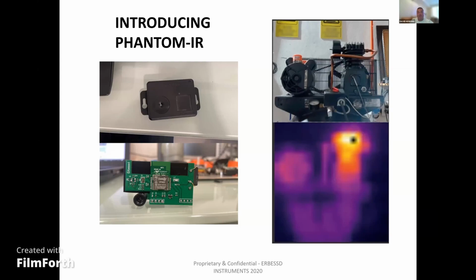The alternative to wearing the arc flash protection is infrared windows. Well, infrared windows are great, but they're also expensive and they require you to be intrusive. You have to cut a hole in your switchgear and install the window. You can only do that during a down period when the switchgear is not energized. So it's a problem if you want to monitor your electrical assets.